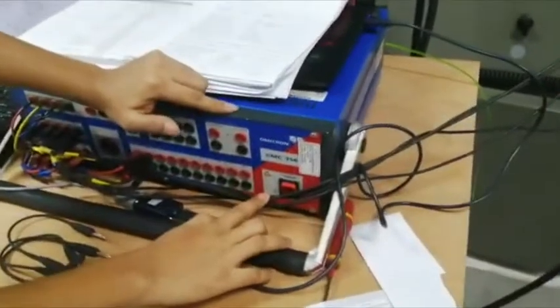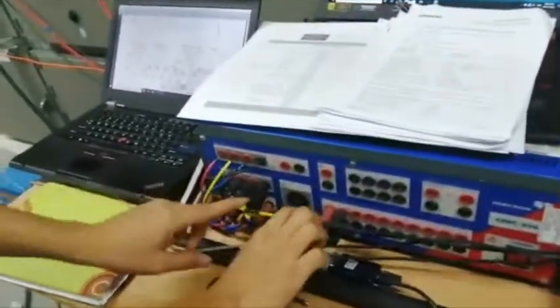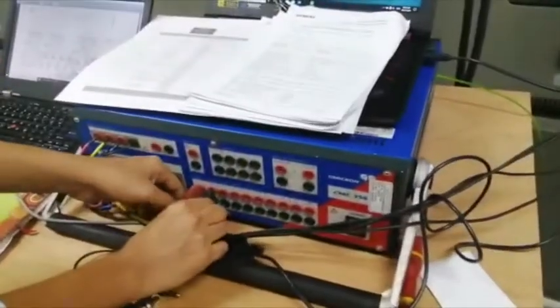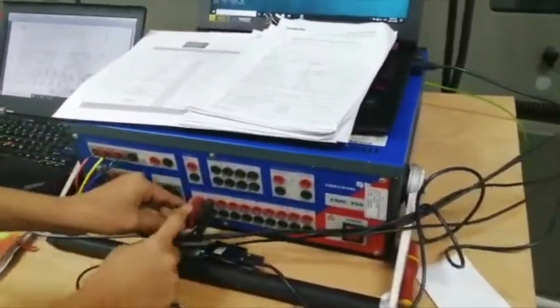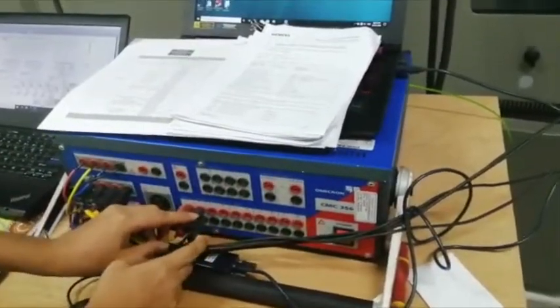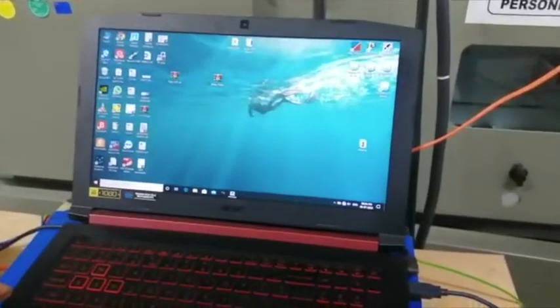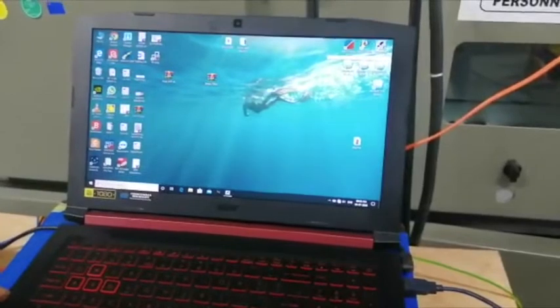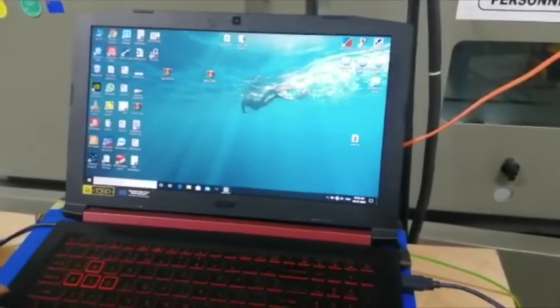Next, for testing, I am using 356 Omicron test kit. We have two sources. First source is connected as a 132 kV side. Second source connected to 11 kV side, and the voltage is also connected for 11 kV side. These two contacts I taken for test kit feedback. This one is pickup and this one is trip pass. I am using DIGSI version 4.94 for relay communication.